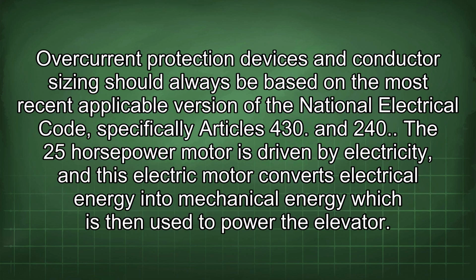Overcurrent protection devices and conductor sizing should always be based on the most recent applicable version of the National Electrical Code, specifically Articles 430 and 240. The 25 horsepower motor is driven by electricity, and this electric motor converts electrical energy into mechanical energy, which is then used to power the elevator.